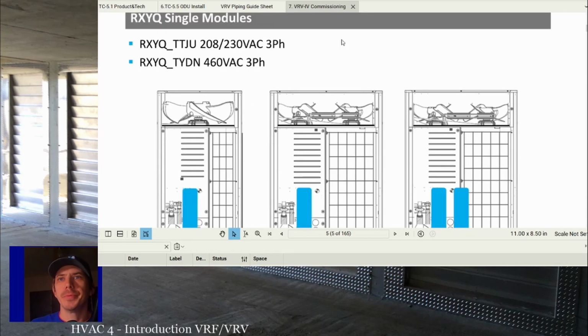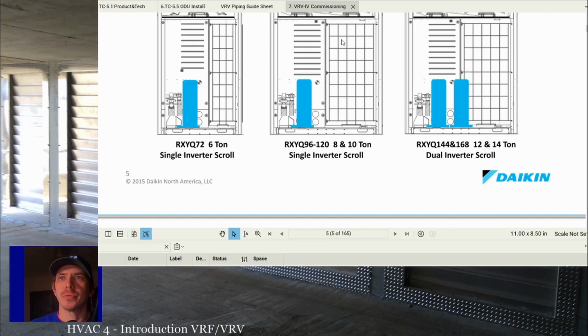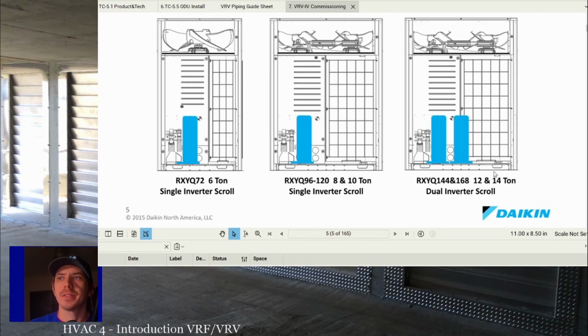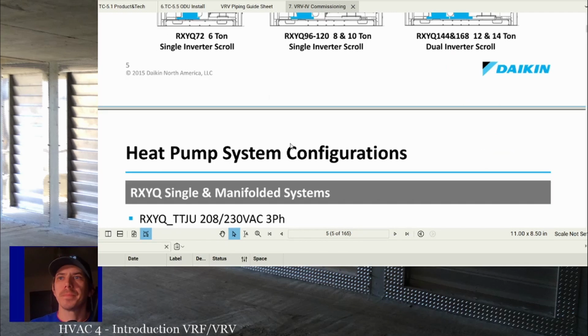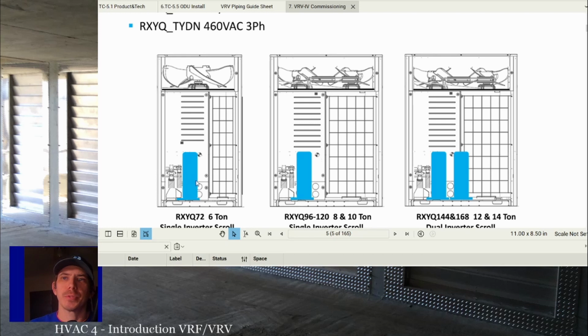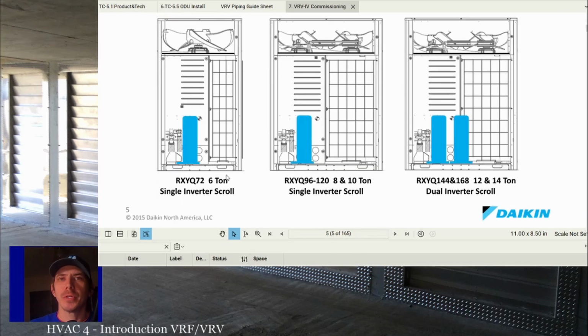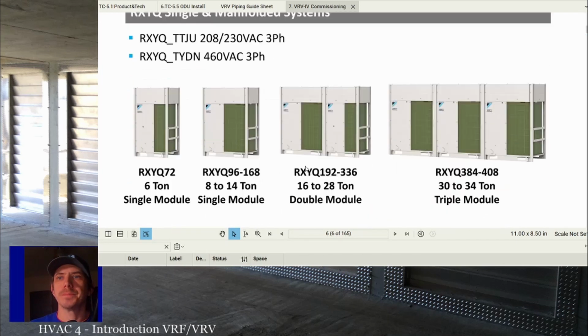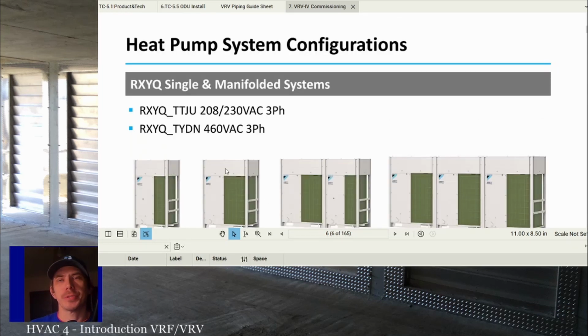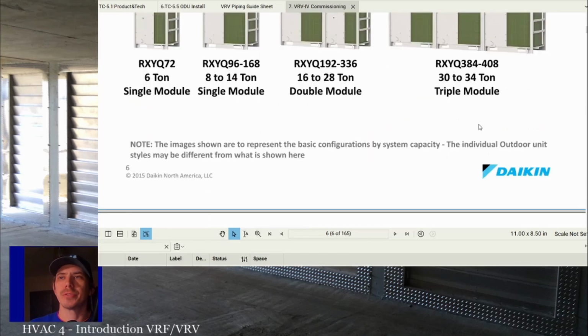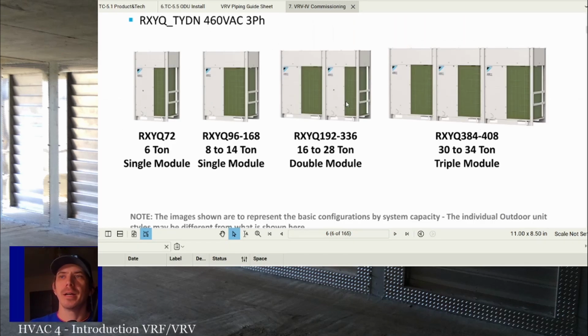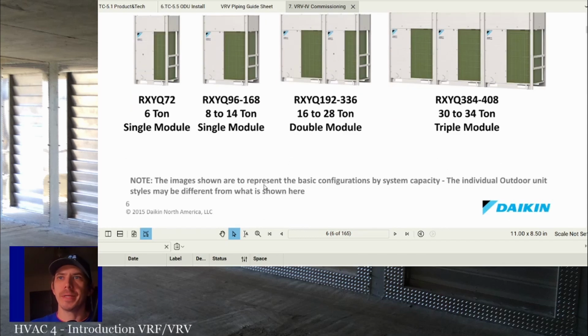The difference between the two is not really the outdoor units. So let's just look at these pictures real quick. They have 6 tons, 8 and 10 ton units, and 12 to 14 tons. So those are their individual units. For Daikin in particular, you have one compressor, two compressors for these different unit sizes. Most VRF units are going to have 1 or 2 compressors in each outdoor unit, as you can see here. So these are heat pumps. Here's a better picture of what they actually look like. And then you can see how you can combine these to create bigger systems. Oh no, sorry. These are single and manifolded single outdoor units. These are triple modules. And you can actually take, say, 3 of these 14 tons and make a bigger system.